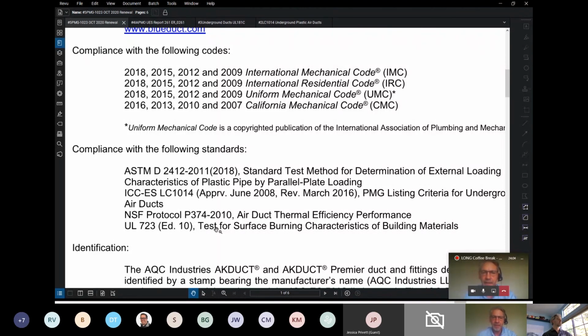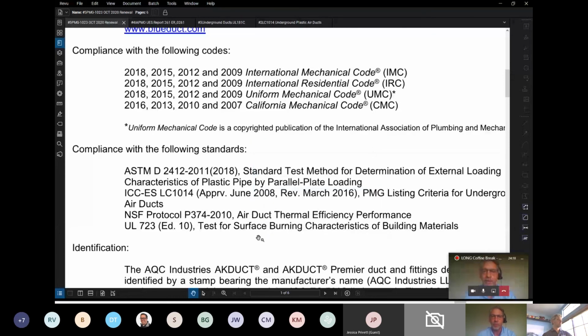What's nice about the NSF test is they move air through at 1,000 feet per minute, then measure the delta T through 100 feet of ductwork, which is far more relevant to your designs because now you're dealing with the other contributing convection and conduction impacts on your delta T. So it's nice to have that within the test — you can be confident there are no other factors impacting your cooling or heating load.